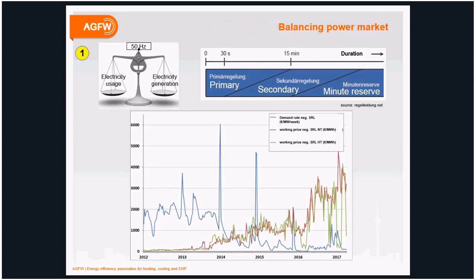Looking at the picture at the bottom of the slide, you can see the different price developments that can be earned by operating power to heat within the secondary balancing power market over the last 5 years. There are three graphs: the blue one describes the average demand rate, the price earned for providing capacity, in euro per megawatt and week. The green and red graphs depict the average working price paid for physical operation of secondary balancing power, in off-peak times in red and peak times in green, in euro per megawatt hour. Looking at the blue graph, you can see why all the listed companies started investing in power to heat in 2012 to 2014 in Germany, where prices were about 1800 euro per megawatt and week without even operating it.